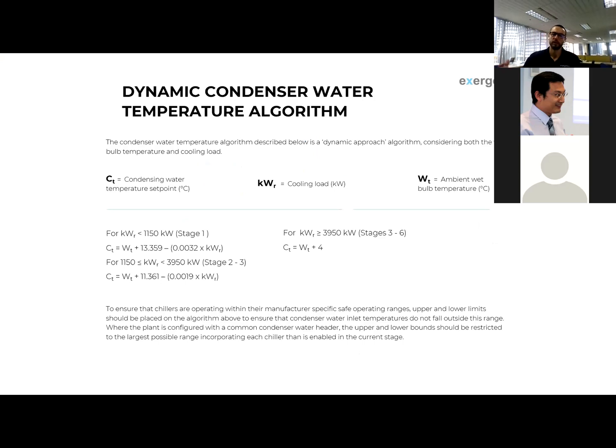So we're letting the model decide, for a given cooling load, I know that my chiller or chillers must produce this much cooling. Then working back from there, what's the difference in COP depending on that lift across the chiller, and is it worth me running my fans harder to extract more efficiency from the chiller, or should I ramp down those fans? So this is what comes out.